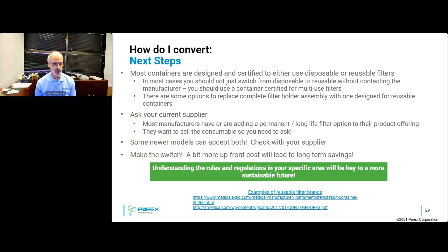There are some newer models out there that have been certified to use both reusable and disposable ones. So again, check with your supplier, and make the switch, because a little bit more upfront cost will lead not only to long-term savings on filter media, but savings within your hospital from reduction of HAIs.